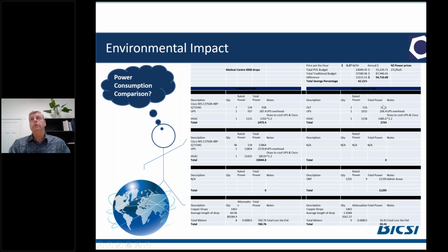And that is the power loss in the cables when using traditional power solution due to the increase in the average drop length. For this particular example I've been talking about, of course, the traditional installation losses equates to, as you can see down here, I mentioned before, 760.76 watts per hour, or 18,258.24 watts per day, or as this facility is 24/7 by 365, a total of 6,664,257 watts per year, or an additional 6,664 kilowatts of energy per year.